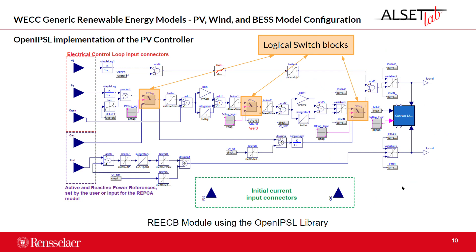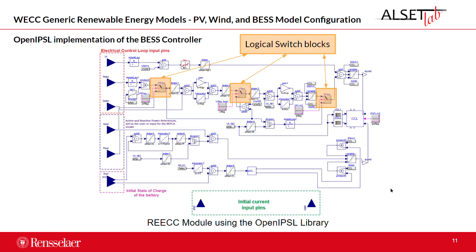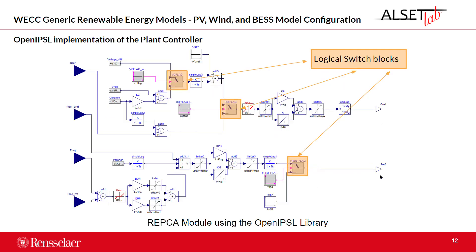This slide shows the electrical controller of the PV and the wind; you can use the same electrical controller for both representations. The orange squares represent logical switching blocks: by changing the Boolean value of a switching block, it will be either opened or closed, representing different control configurations. This is an example of the electrical controller of the battery energy storage system; the main difference is that this component has an initial state of charge of the battery. Finally, we have the REPCA module, also implemented in the OpenIPSL library, which performs the plant controller function of the models.